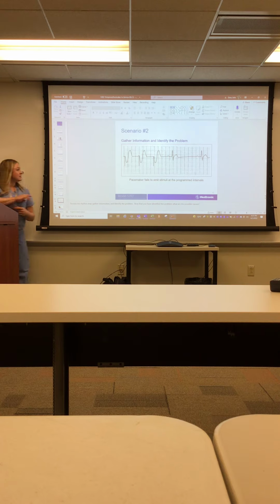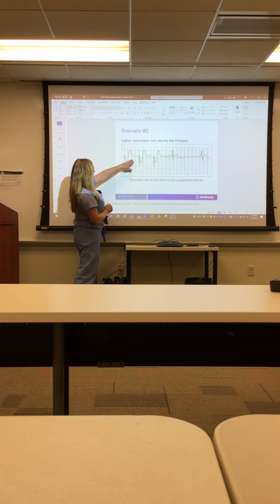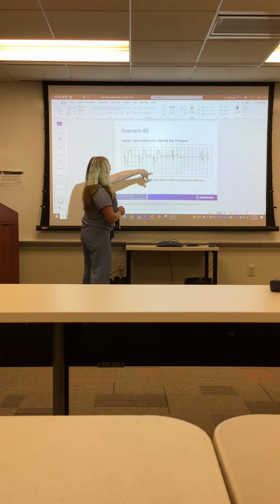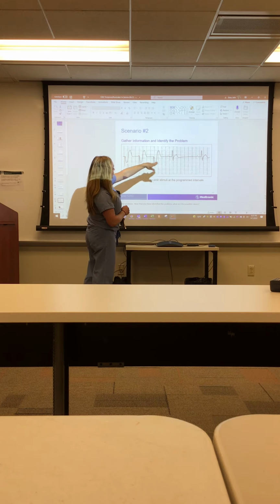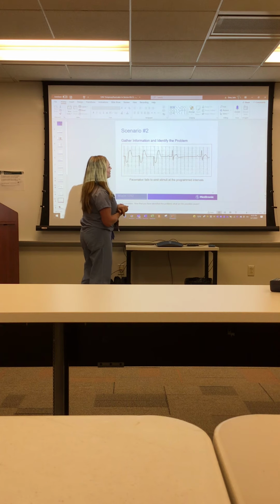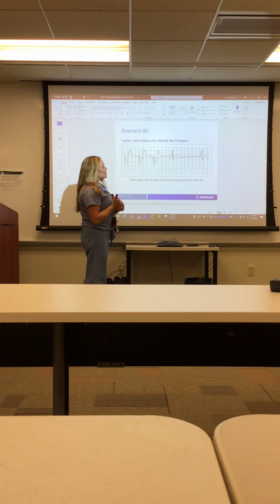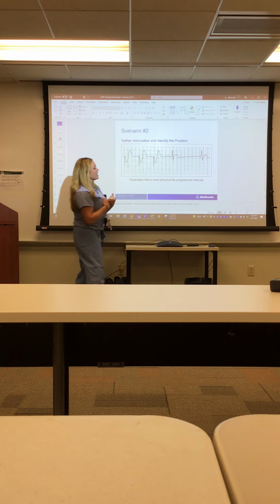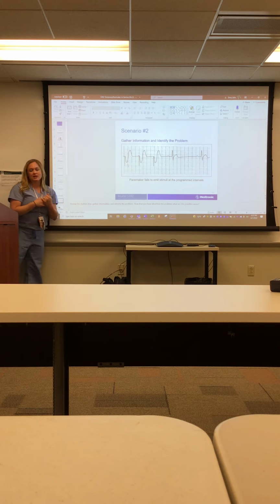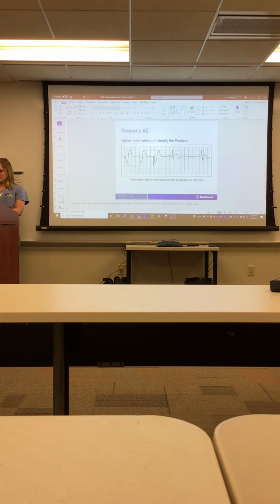So we see these pace beats here, and then we see an intrinsic one come through, and then way too long of a delay. So we don't see a pacer spike, so I don't think output. We don't see anything, but that's way too slow of a rate if we're programmed there. So what do you think the device might interpret that as, or why would it think it was okay? It's oversensing. Oversensing, underpacing. Yep, you got it.